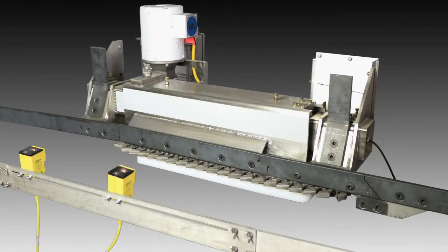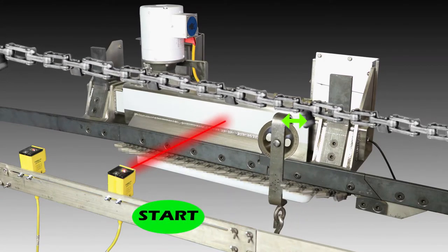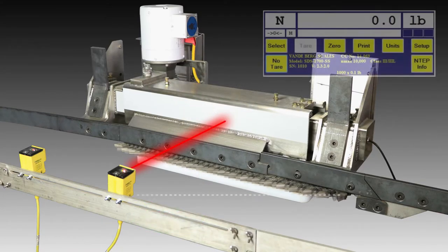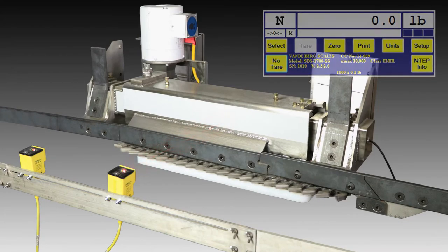Start and stop photo-eyes are mounted on an adjustable slide bracket across from the scale rail and facing a reflective strip. The trolley is ahead of the pusher dog once it reaches the start photo-eye that is mounted across from it towards the beginning of the live rail. At this point, a signal is sent to our SDS weight indicator telling it to start the weighing cycle.